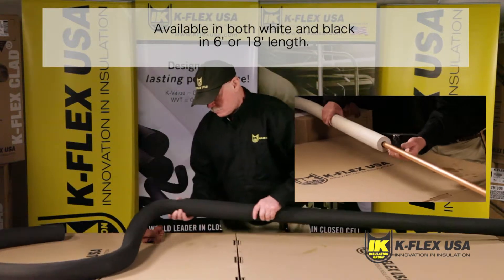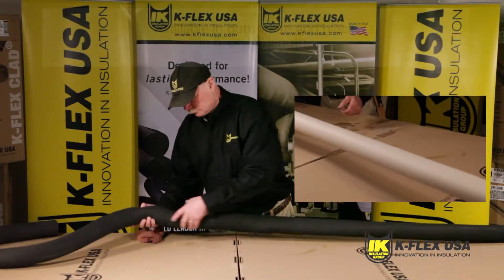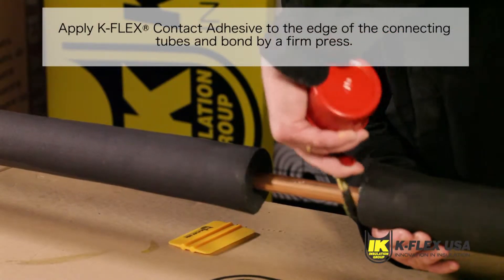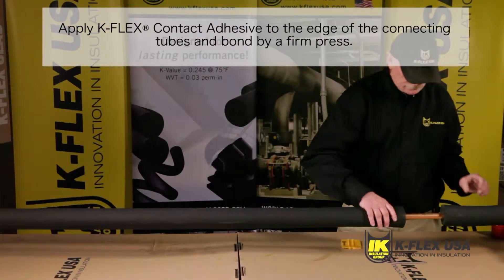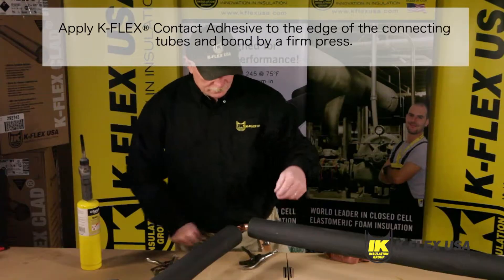Kflex USA offers non-slit tubes in 6 and 18-foot lengths in black and in white for an improved appearance. Grab the connecting tube with insulation and slide it onto the pipe. Apply Kflex contact adhesive to the edge of the tubes. Allow it to become tacky and bond the two tubes with a firm press.